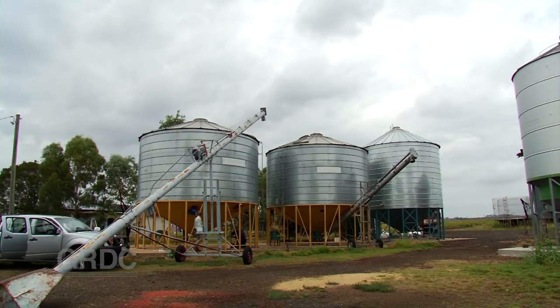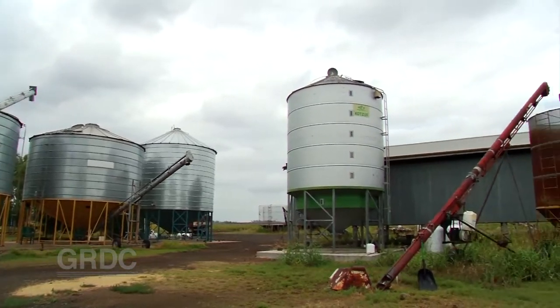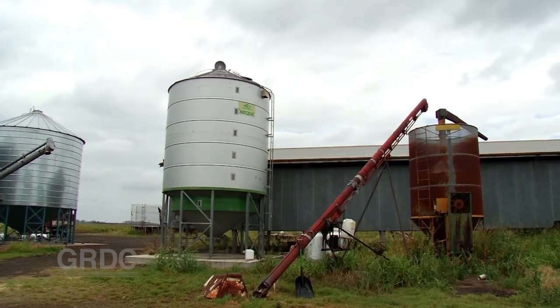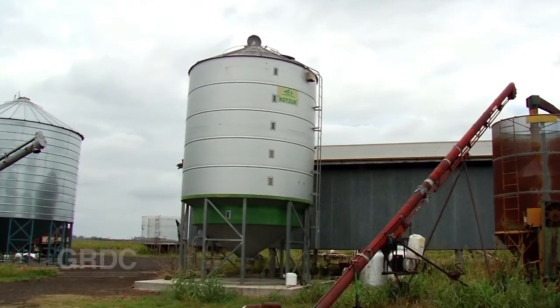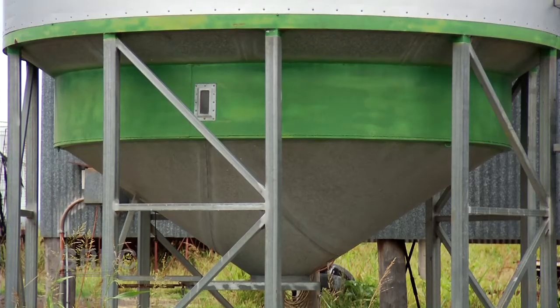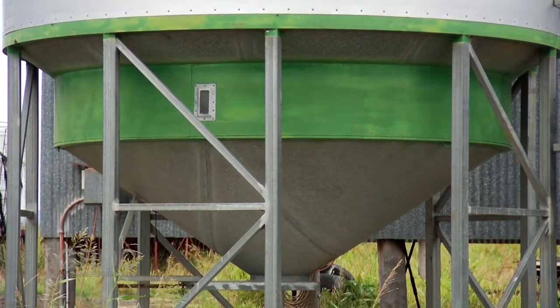Equipment choice is very important. With aeration drying we have a choice. We can go to purpose-built silos for aeration drying. An example is a Kotzur 60 tonne aeration drying set up with a three-phase 7.5 kilowatt motor, because we're looking for much higher air flows for aeration drying. The sort of air flow rates we're looking for are somewhere between 15 and 30 litres per second per tonne. This gives the reliability to aeration drying.